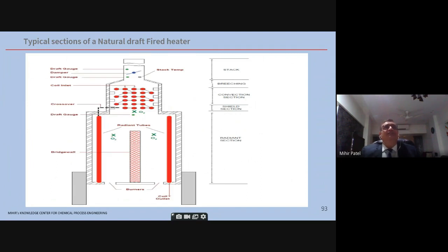Typical sections of a natural draft fired heater. So you see the radiant section at the bottom. Above that, you have the draft gauge and the radiant arch. The crossover is there. The shield section, as I mentioned, the three bottom rows of the convection section are unfinned, called shield tubes. Then the convection section, and then finally the damper. This is a natural draft heater, of course. The ID and FD fans are not there.